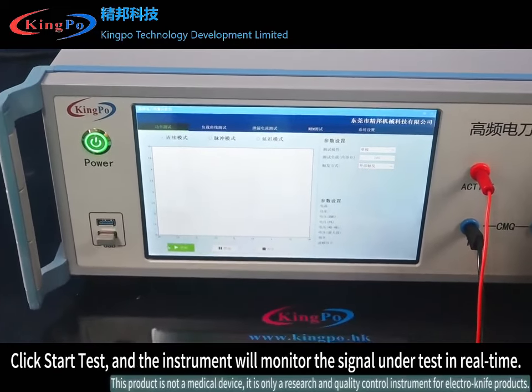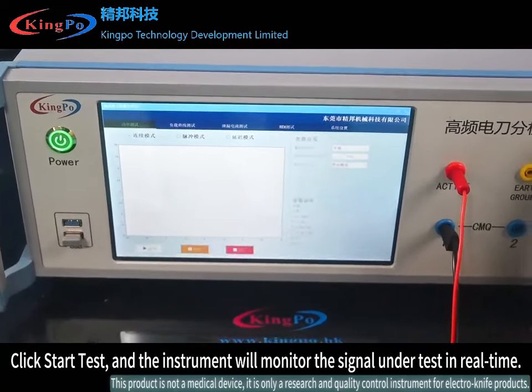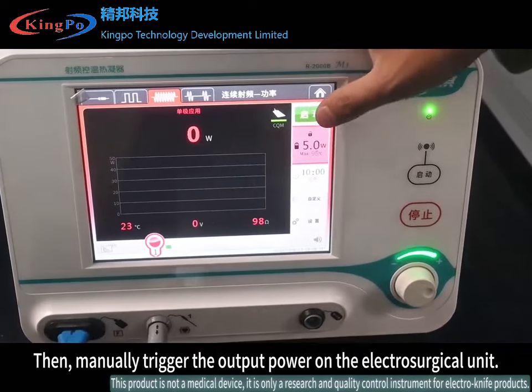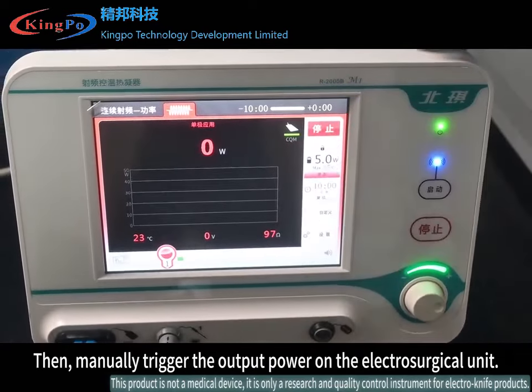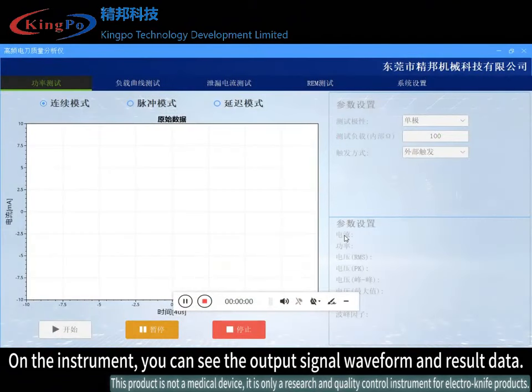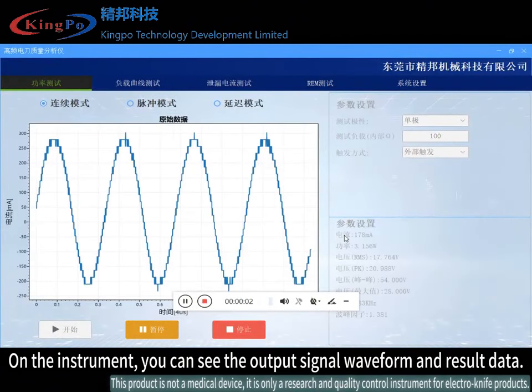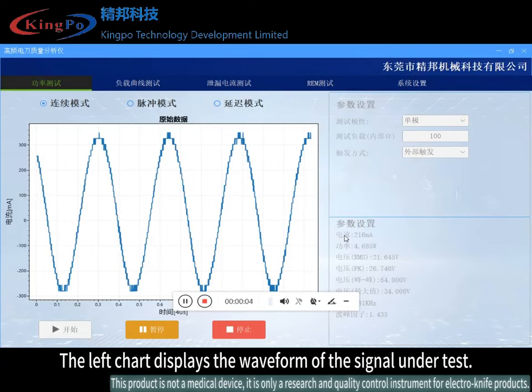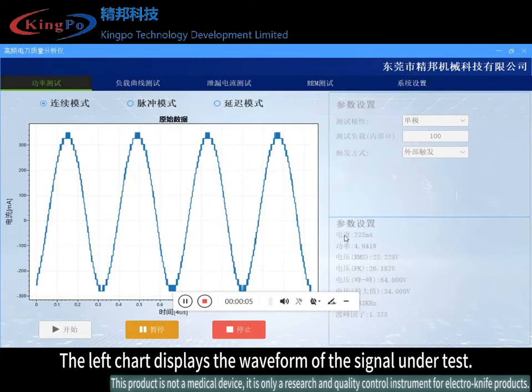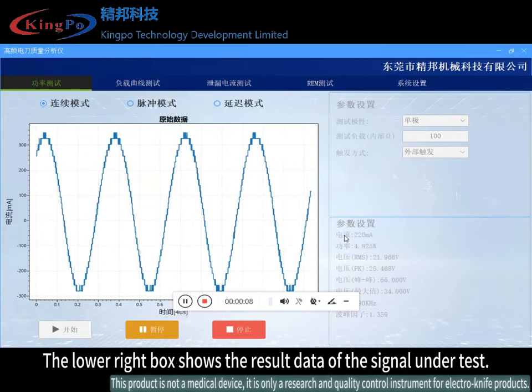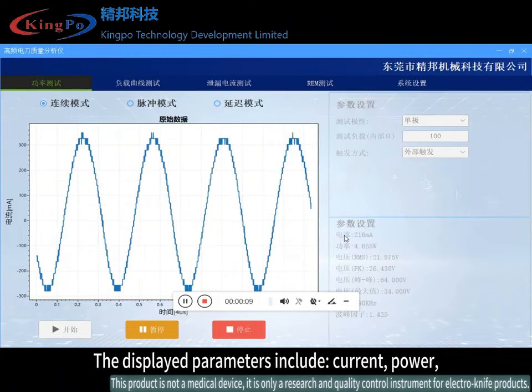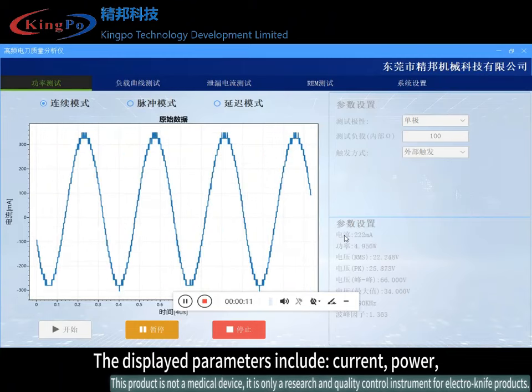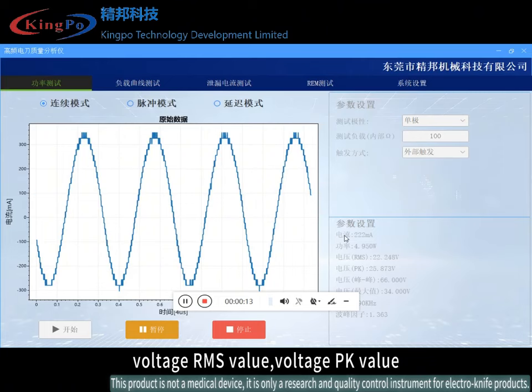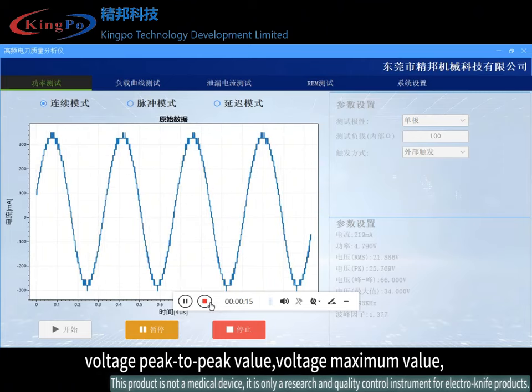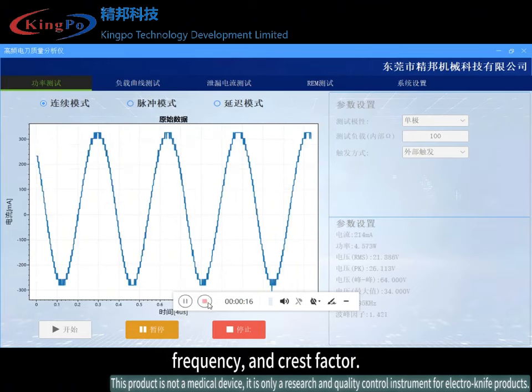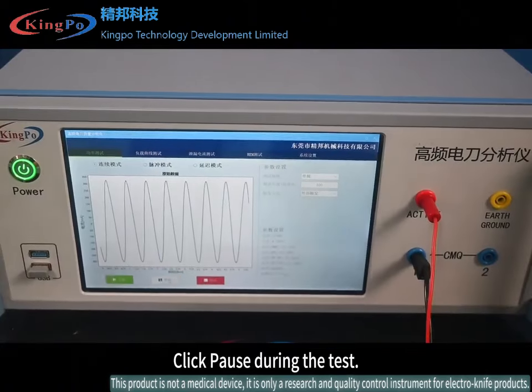Click Start Test and the instrument will monitor the signal under test in real time. Then, manually trigger the output power on the electrosurgical unit. On the instrument, you can see the output signal waveform and result data. The left chart displays the waveform of the signal under test. The lower right box shows the result data of the signal under test. The displayed parameters include current, power, voltage RMS value, voltage PK value, voltage peak-to-peak value, voltage maximum value, frequency, and crest factor. Click Pause during the test.